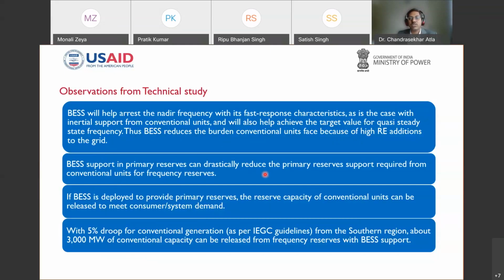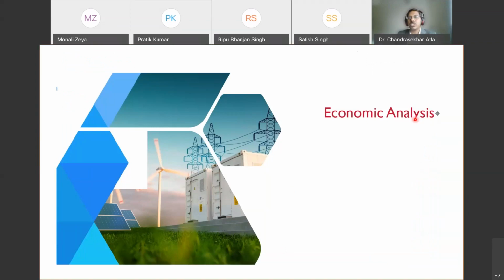BESS support in the primary reduces the support required from the conventional units. So that is another advantage here. Whatever the BESS provides, the conventional units can be released for regular scheduling purposes. So with the 5% droop that we have considered, around 3000 megawatt of conventional capacity can be released from the frequency reserves with the support of BESS. So this is what we have made from the analysis, and I request Anish to take over the economic analysis.